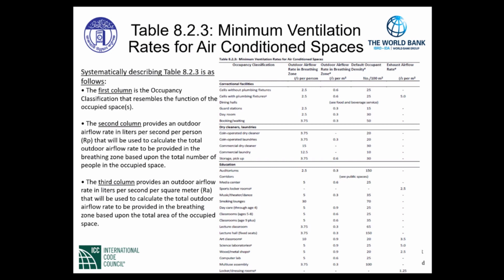The second column provides an outdoor air rate in liters per second per person. The outdoor airflow rate, we can say, has a variable that we'll title R sub P, the rate of airflow per person. We will use this to calculate the total outdoor airflow rate to be provided in the breathing zone based upon the total number of people in the occupied space. So simply looking into the second column of the table, as seen here, based upon the occupancy classification and the space within the occupancy, you are given a prescriptive outdoor airflow rate in the breathing zone in liters per second per person. Let's take an example.